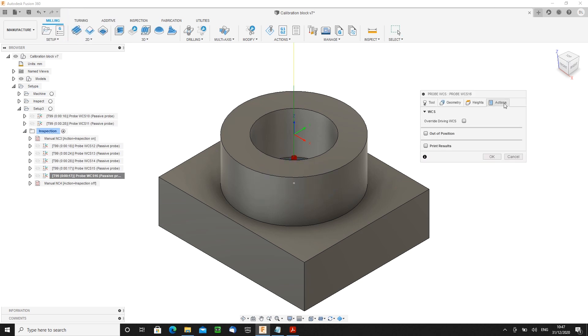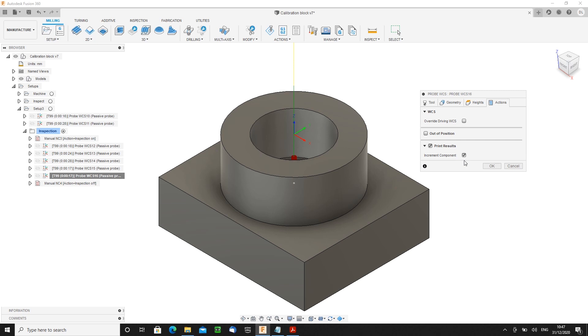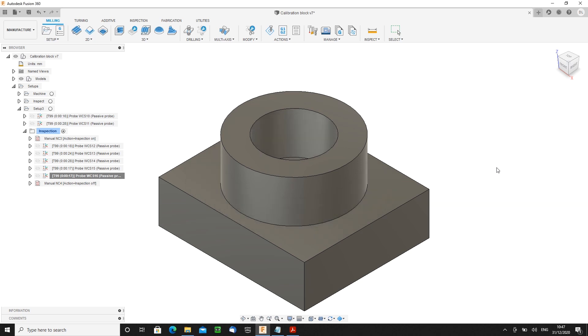Okay, now there's one last stage we have to do because I wanted the two parts that were going to run one after the other separated into different tables. I need to pick the last one, go to the Actions tab, select Print Results, which is a nuisance, and say Increment Component. That will cause it to break the table and the output and produce a separate table for each iteration of the whole program. And that's as done.